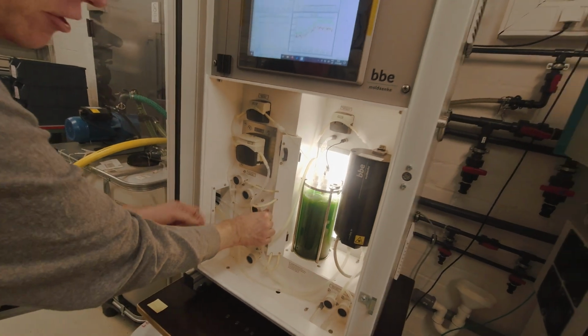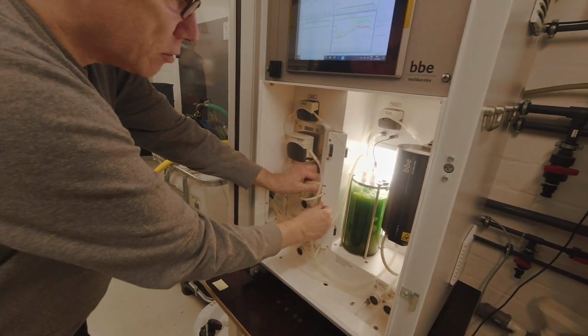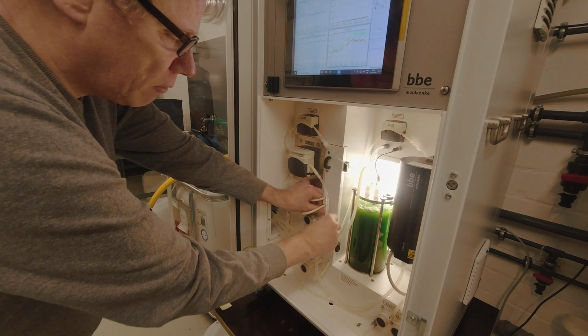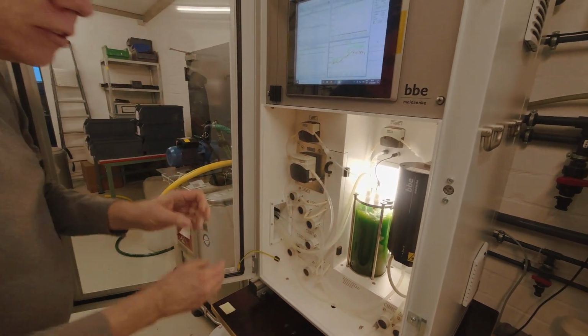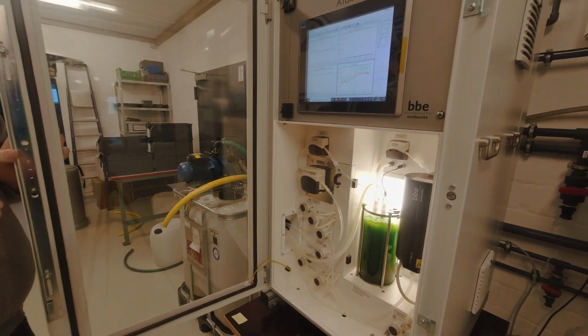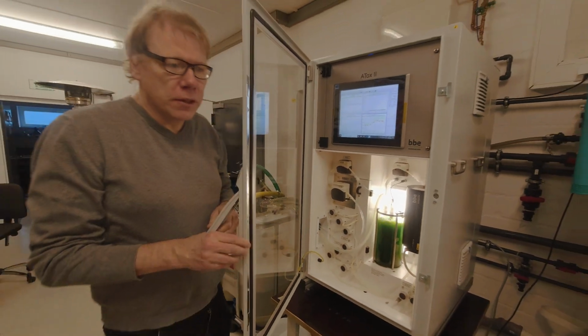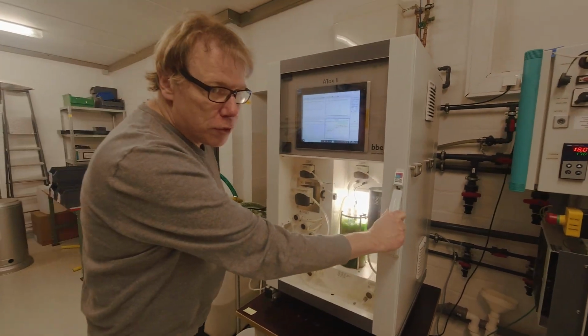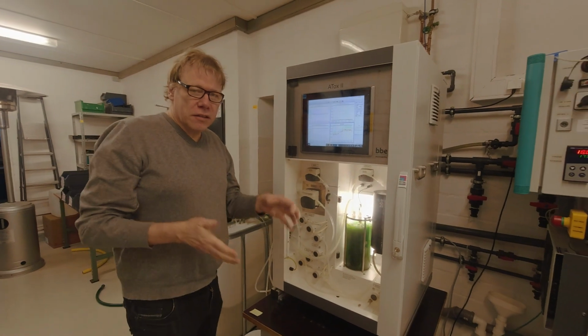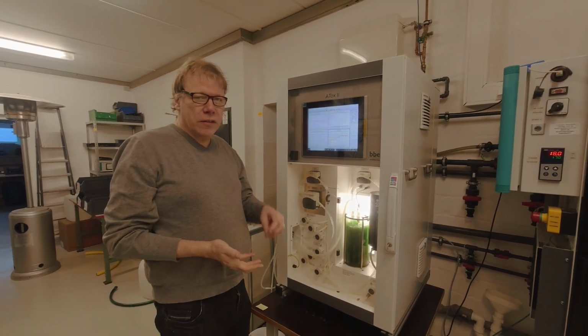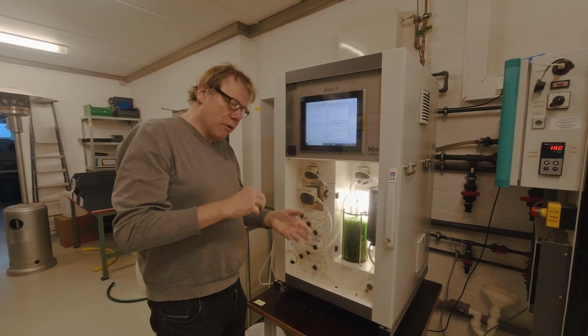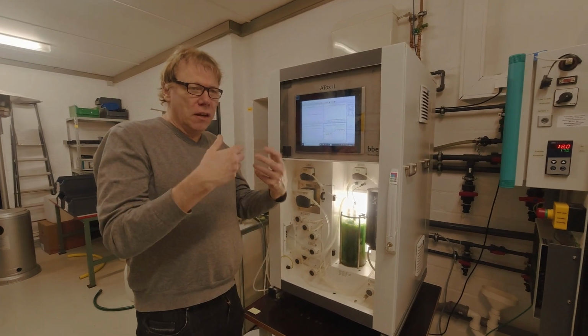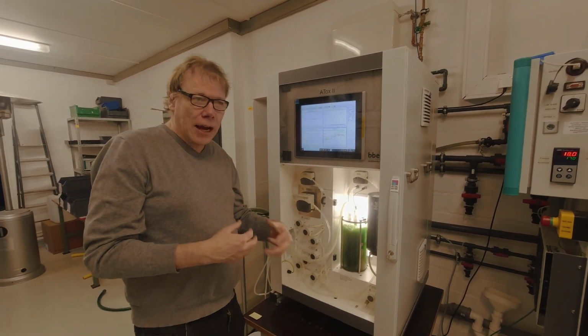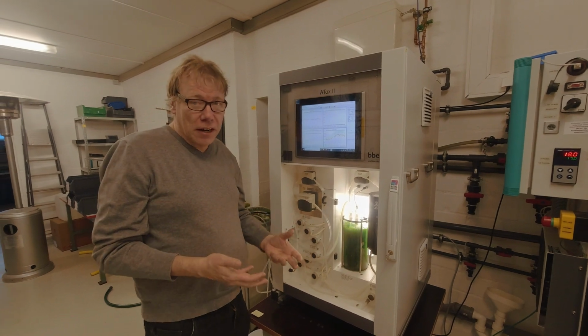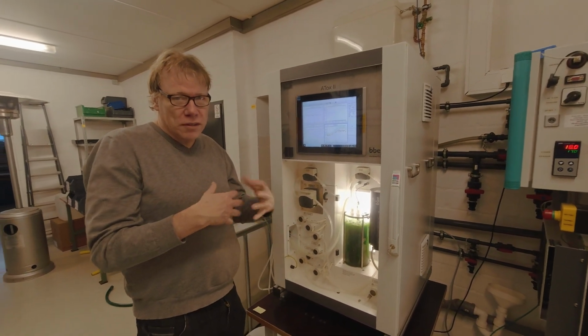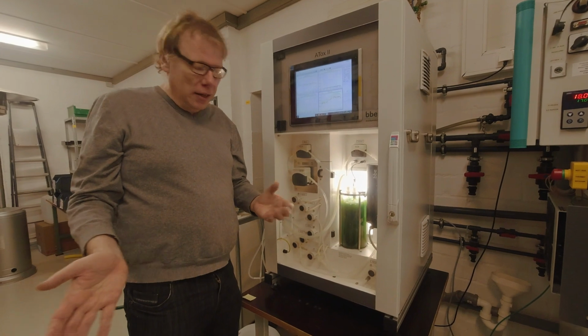where we store the solution of algae and reference water or sample water for a certain time. In the standard configuration, we store it for 20 minutes there, so that there is time for the reaction of the algae in the sample or in the reference water to adapt and also to take up the toxin if it's there, and you have a reaction within, in this case, 20 minutes.